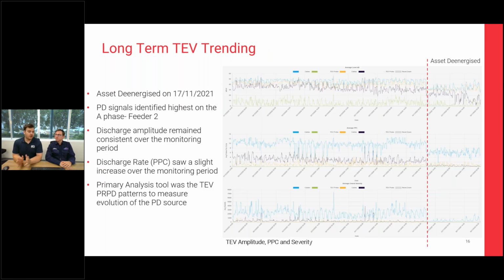These are the plots we received back from the Astute monitor, 2-minute data for amplitude, pulses per cycle, and severity, looking at each of the 3 phases. The blue line at the top represents feeder 2 phase, and it's relatively consistent. It did go up and down a little, which may have been due to load, temperature, or parts thermally expanding inside the CT. We couldn't draw a solid conclusion on what was causing it.